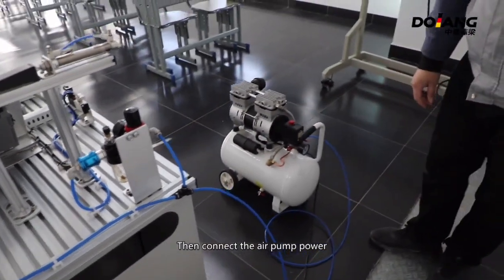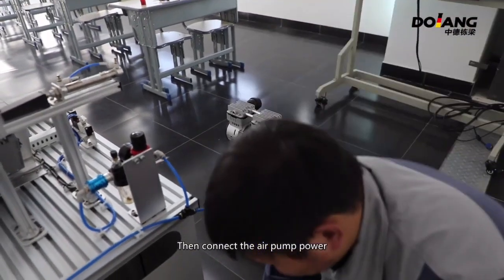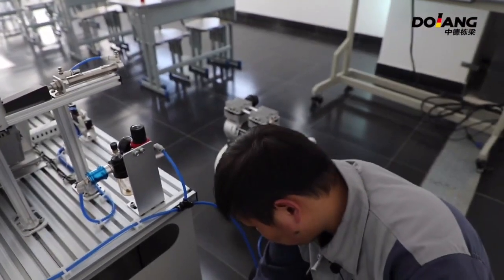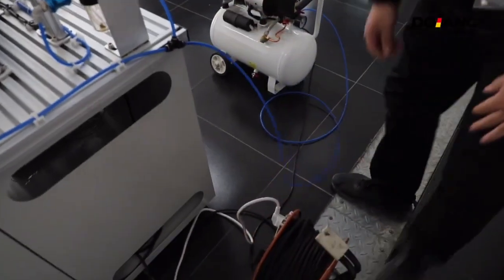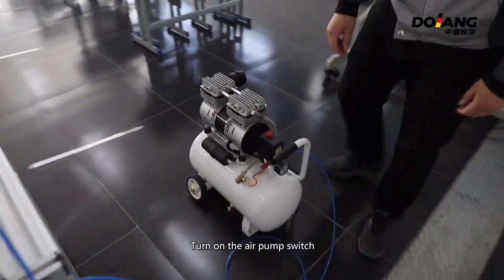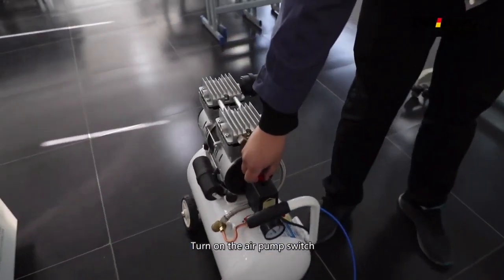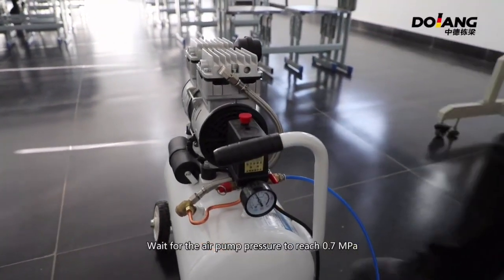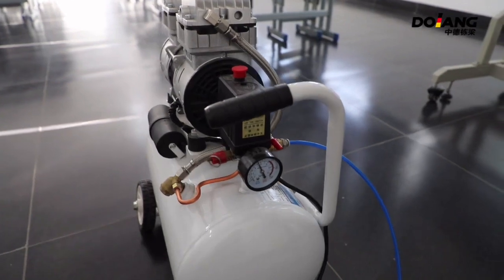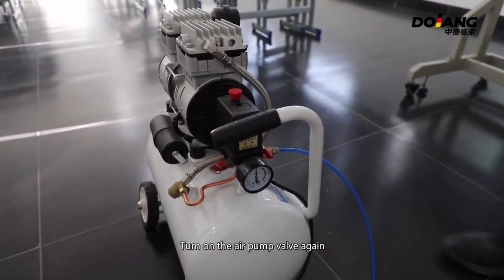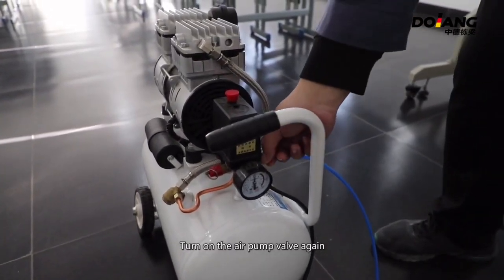Then connect the air pump power. Turn on the air pump switch. Wait for the air pump pressure to reach 0.7 MPa. Turn on the air pump valve again.